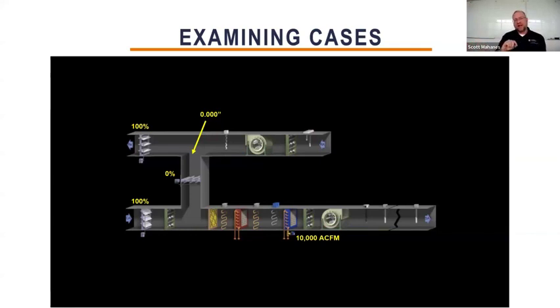And so if I have a calibrated flow station, or if I do a measurement of airflow on the discharge side of this unit at 10,000 CFM, can I calibrate the outside airflow station to the same value I see on the supply? Oftentimes I used to do this. But what if I told you the outside air needs to be 10,980, not 10,000? And these are the conditions you need to be at to get those values.